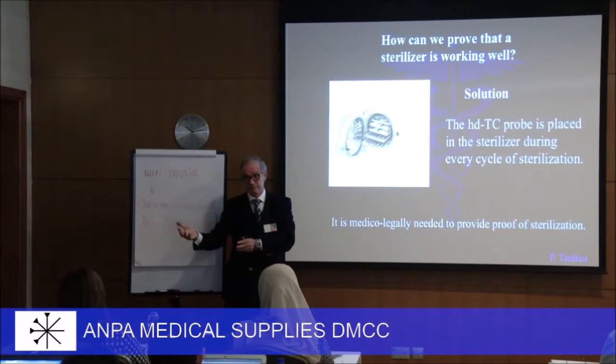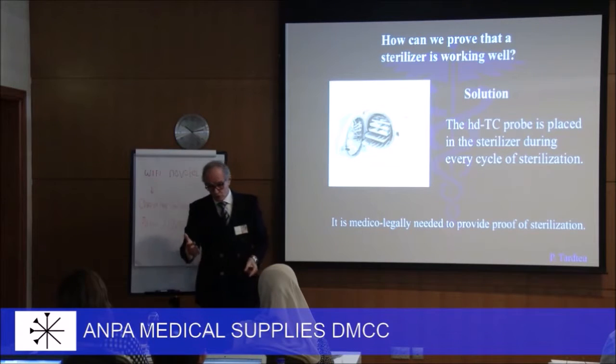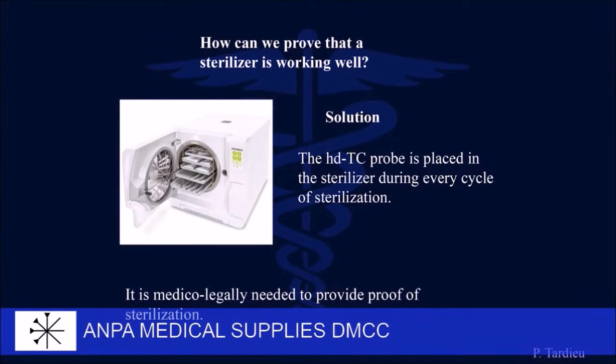That's another thing. To avoid this, we place a probe inside the sterilizer for every single cycle. So every single cycle must be validated.